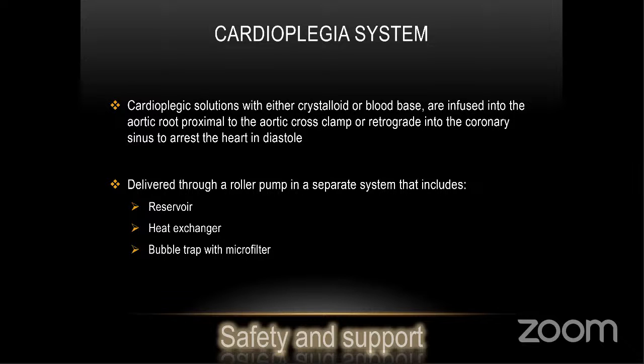The cardioplegic solution is usually delivered through a roller pump in a separate system that includes a cardioplegia reservoir, heat exchanger, and bubble trapper with microfilter.